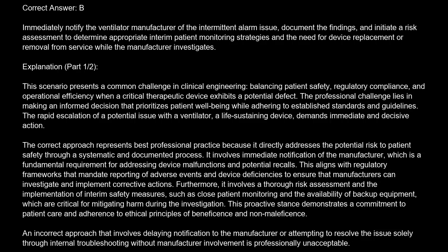The correct approach represents best professional practice because it directly addresses the potential risk to patient safety through a systematic and documented process. It involves immediate notification of the manufacturer, which is a fundamental requirement for addressing device malfunctions and potential recalls. This aligns with regulatory frameworks that mandate reporting of adverse events and device deficiencies to ensure that manufacturers can investigate and implement corrective actions.